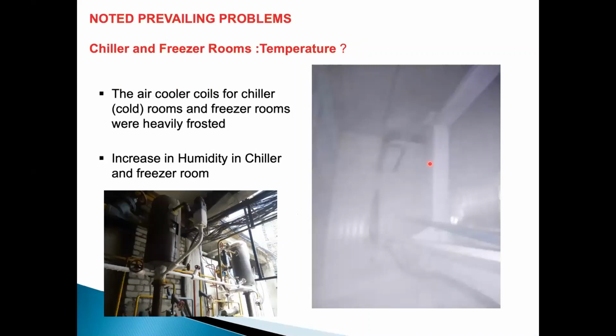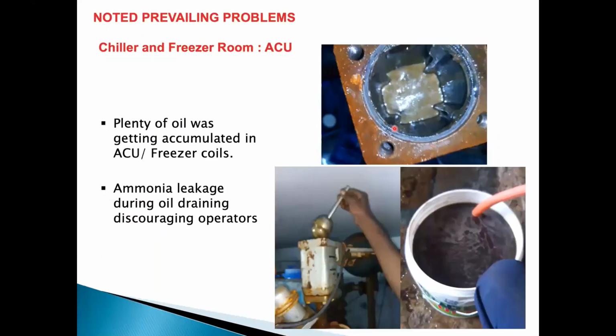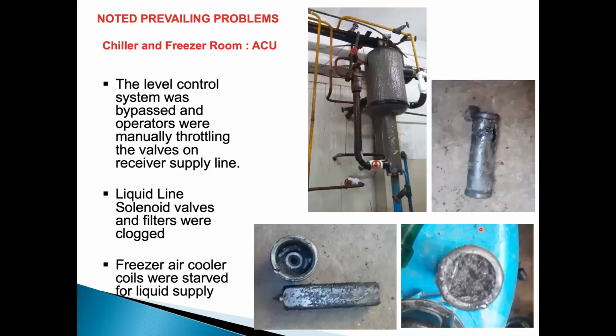There was huge frosting happening, and because of this frosting, humidity heavily increased in the chiller rooms. So most of the chillers or the ACUs were not operating, and their capacities were not reaching. It was full of oil. You can see here how much oil it was filled with. The evaporator was filled with oil, and you can see how much oil was leaking. A lot of ammonia was leaking when this oil was drained. The freezers' capacities were not achieved.